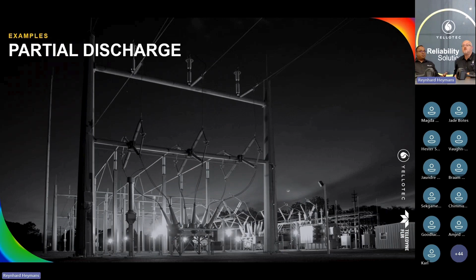Okay, so let's go through some examples of partial discharge. The first thing you'd note is the wide field of view on this camera allows you to scan a complete substation a lot faster with pinpoint accuracy. Okay, if you've got multiple discharge points, you're able to pick up multiple discharge points at the same time. You can then subsequently pinpoint exactly which one you want to look at and go to that and do a proper survey on that. Okay.